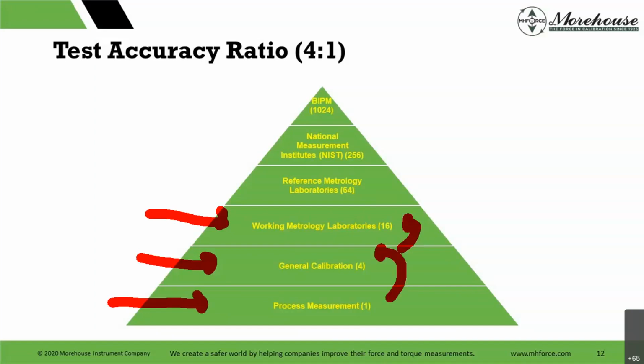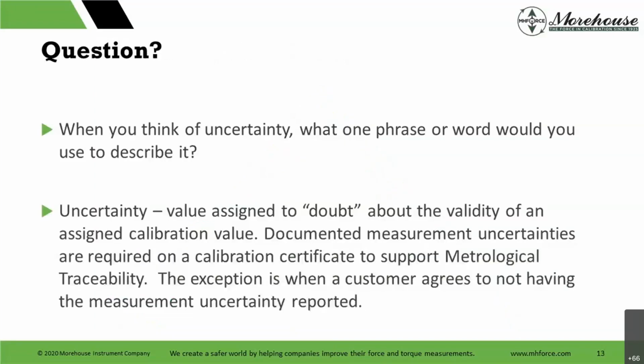It's very, very rare. So in short bursts, these T.U.R.s can work. There are several standards that are written, like ASTM E74, that rely on it. But it is a confined approach that says, hey, we're going to be 4 times better, 5 times better, 10 times better, and we're going to build our pyramid out, and we're going to do it in the standard. So very different than general calibration, where you're looking for someone that's 4 times better. And if you think about it, they have to be 4 times better, then who calibrates their stuff has to be 4 times better, and so on. As you can see by this pyramid, it just does not work.